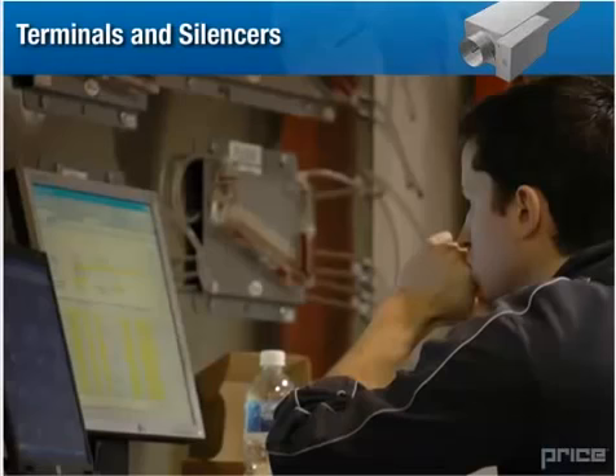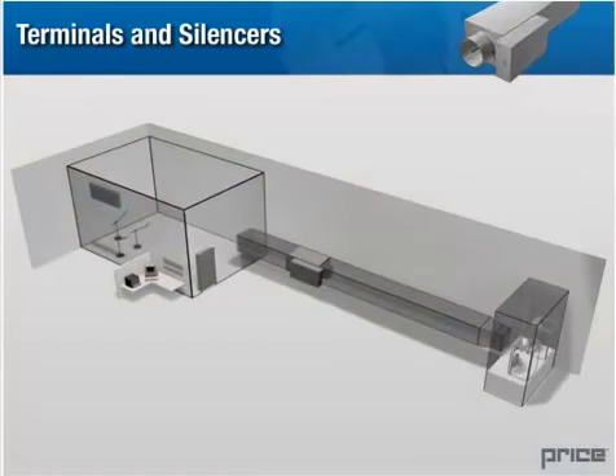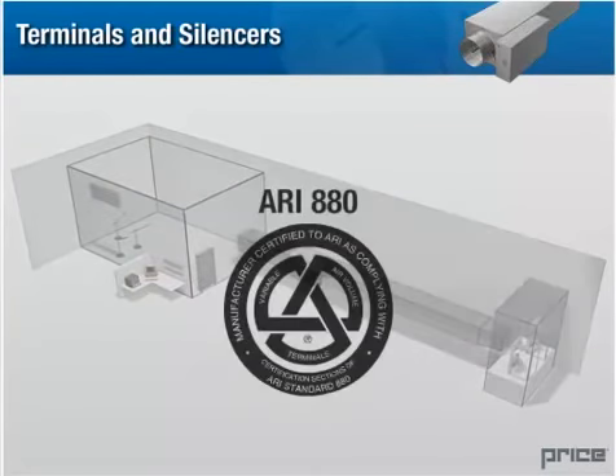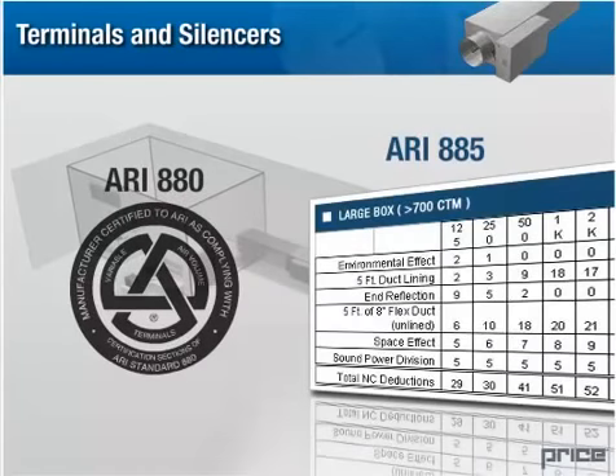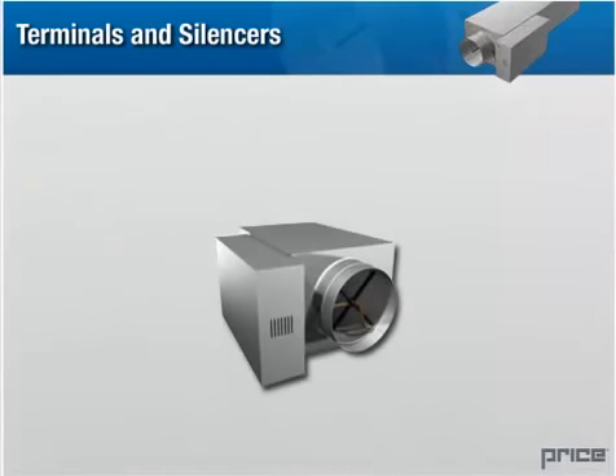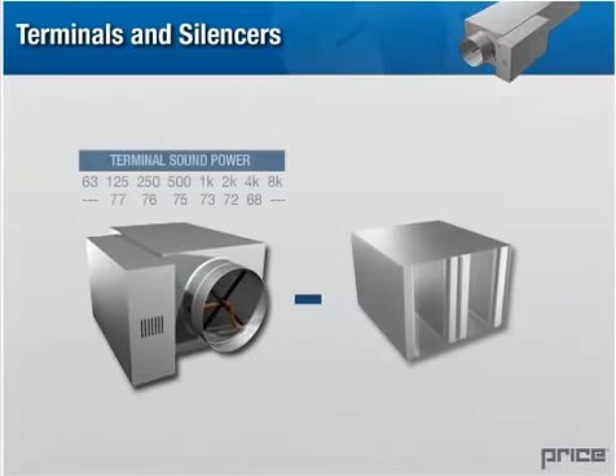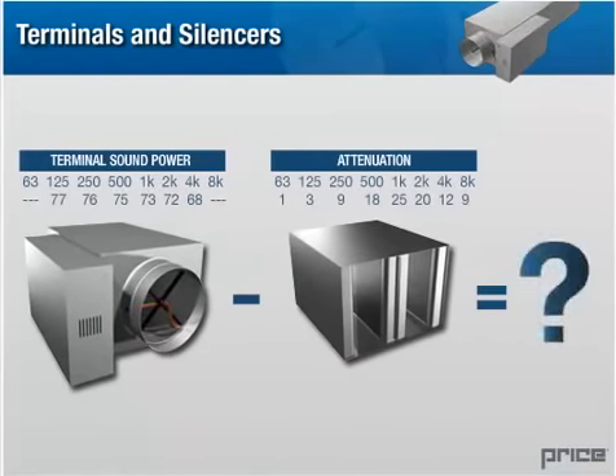Terminals and silencers. As noted earlier, an integral part of the HVAC designer's job is to be able to predict sound levels of terminal units and produce an NC rating. Predictions are often made using the terminal unit test data that is obtained in accordance with the ARI 880 test method, incorporating standard ARI 885 duct calculations to get the resultant NC levels. The addition of silencers into the system means that the sound power deductions for silencer insertion loss and sound power additions for silencer generated noise must now be incorporated in order to determine the NC level.